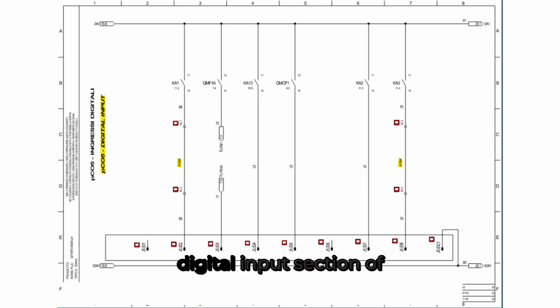This page covers the digital input section of the Carel PCO5 Plus controller, which is responsible for receiving on-off signals from relays, contactors, and safety devices throughout the heat pump. At the top, we can see the 24-volt supply, labeled 16.8, feeding across multiple input channels. These 24-volt lines act as reference voltage for the controller's input terminals, allowing it to detect whether a circuit is open or closed.